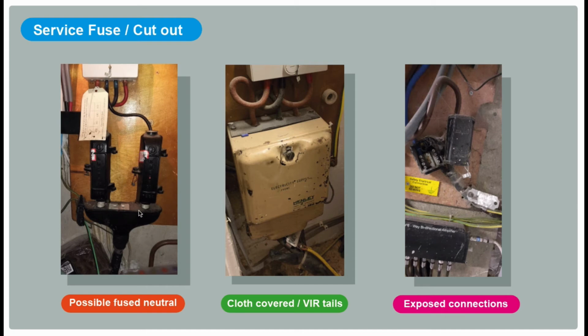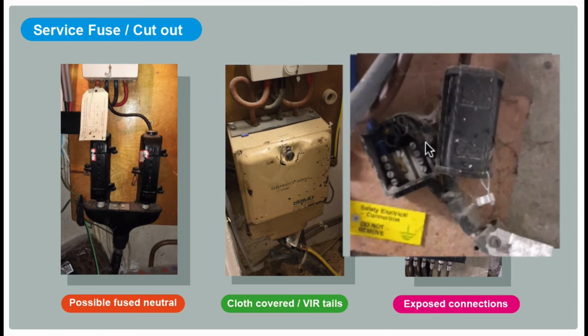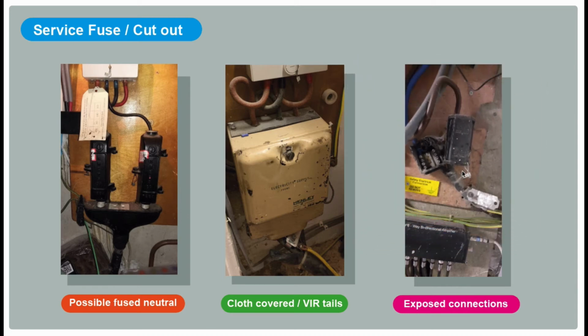It's also a cast iron head. There might be old tails, cloth covered or VIR tails, vulcanized India rubber. These can perish and disintegrate over the years, and this is many decades old, so that might need upgrading. And also, we often find on Wylex blocks the cover's missing. I see this quite often. This is in the neutral here. That needs to be sorted out as well.